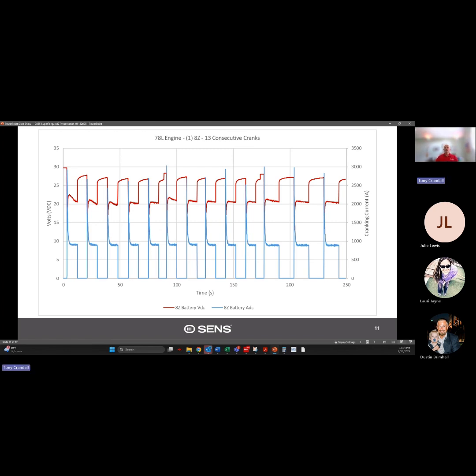What you see on the screen is a diagram for a 78-liter engine, which is a 2 megawatt generator. That generator had one SuperTorque 8Z connected to it. Two points of note: we did not have an AC power source recharging the 8Z during this test sequence, and we had the fuel starting solenoid turned off on the generator to ensure it would not actually start. We weren't necessarily trying to simulate a failure of the 8Z, just trying to find out the limitations and feedback data points if it experiences numerous cranking cycles over and over again without recharging.